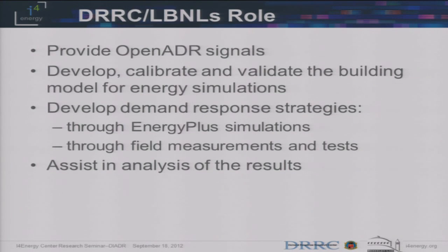And the baseline modeling issue that David just mentioned is one that we've spent a lot of time on also. And there's a lot of ways that you can deal with baselines. The baselines have to do with timescales of your performance predictions. So in a lot of the projects we do, PG&E will look at the last 10 days to compare how you did on one day with the previous 10. You can use weather regressions, or you can use models of how you would perform compared to some baseline. But in ancillary services, you may have an even faster need for baselines. You may have a real-time baseline tracking the performance against some baseline.